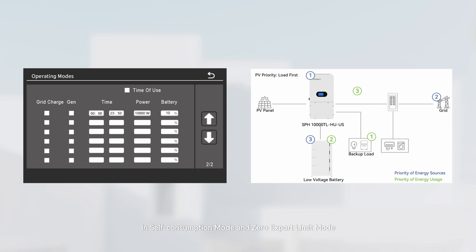In self-consumption mode and zero-export limit mode, the battery discharge power adjusts dynamically based on load consumption. There will be no export of excess battery power to the grid, even if the load demand is lower than the set value and the PV sell function is enabled.